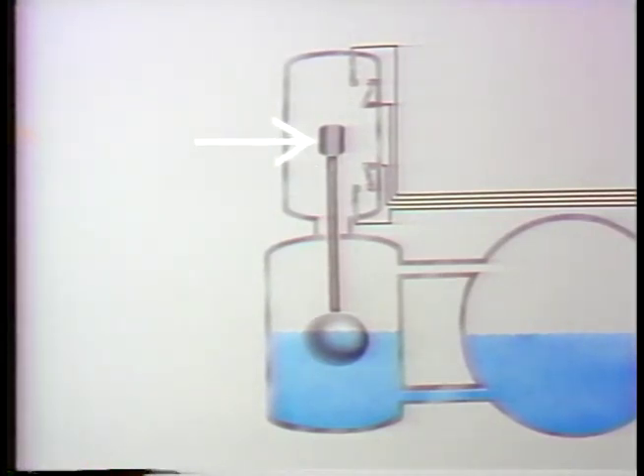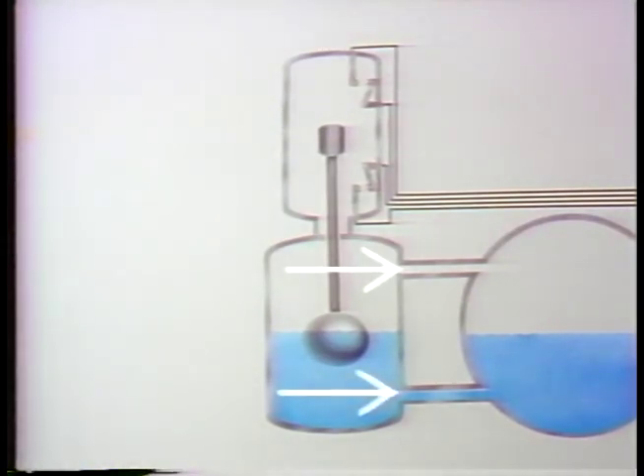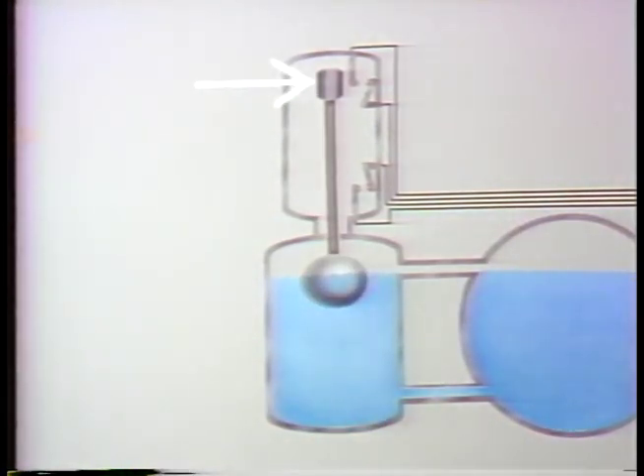A magnet is attached to a rod which is operated by the float. The chamber containing the float is connected to the feedwater heater by top and bottom connections. As level in the feedwater heater changes, so does the position of the float. If level increases, the float and the magnet rise. When too high a level is reached, the magnet's attraction closes contacts, completing an electrical circuit, which then initiates a high-level alarm. If water level decreases and drops too low, the magnet closes another set of contacts, initiating a low-level alarm.